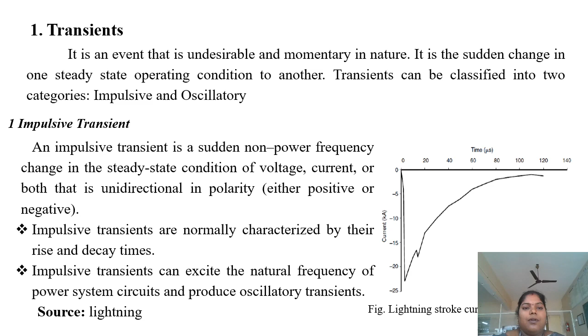Next one, oscillatory transients. Oscillatory transient is nothing but a sudden non-power frequency change in steady state condition of voltage, current or both that includes both positive and negative polarity values. Oscillatory transients are again classified into three types: high frequency transient, medium frequency transient, low frequency transient. High frequency transient means the frequency component is greater than 500 kilohertz.